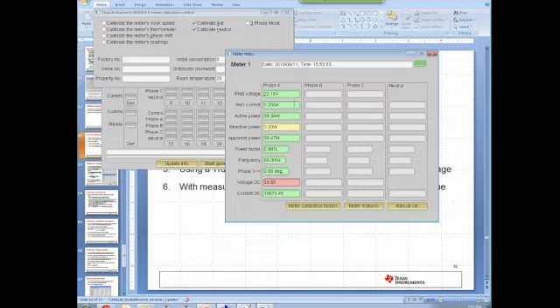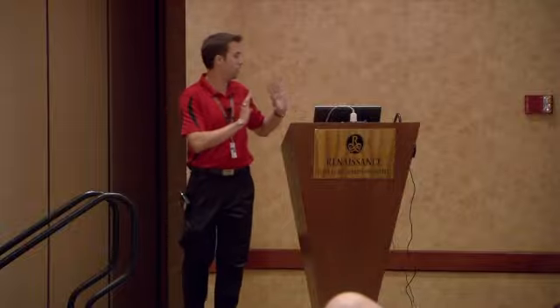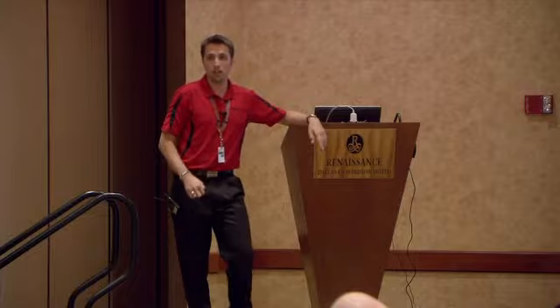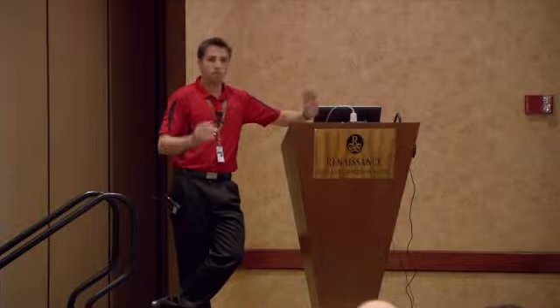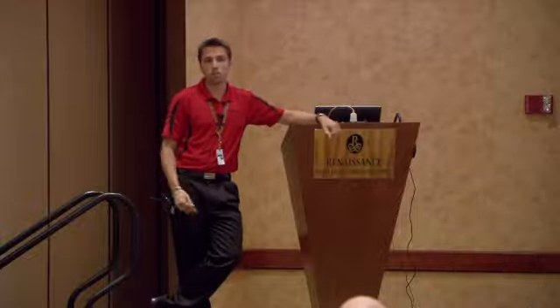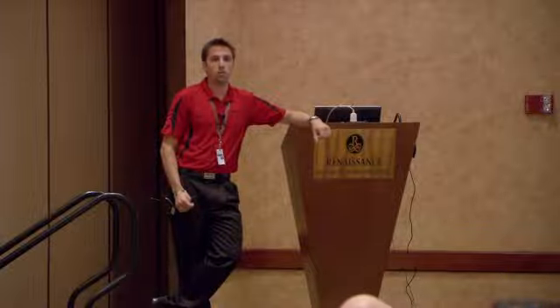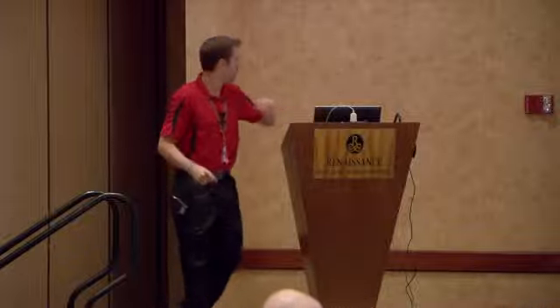So now that we have power coming in, I would like people to treat these as if they're high voltage. Right now, I know it's only 24 volts coming in, but if you're sitting down with a customer, it's probably going to be 120 or 240. So this is where you go hands off the meter and only talk to it via this calibration GUI here. If you do have to get close to it, we have the probes here that we're going to be measuring in a bit. So make sure that you're really careful whenever you get in there. You need to make sure that you don't accidentally touch any of the high voltage sections.